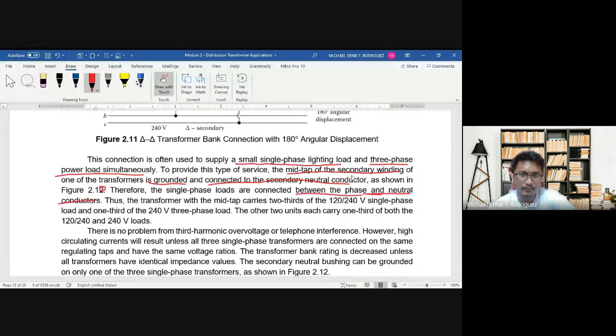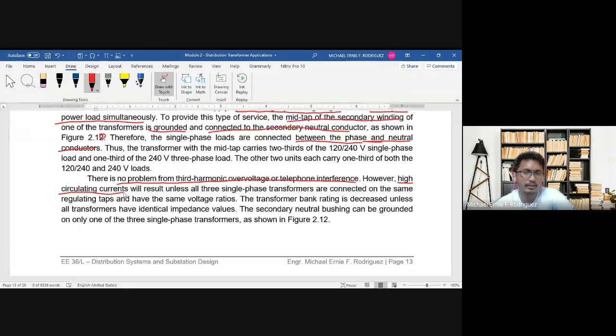For a delta-to-delta connection, you don't have a problem from third harmonic overvoltage or telephone interference. But the problem we have is high circulating currents.